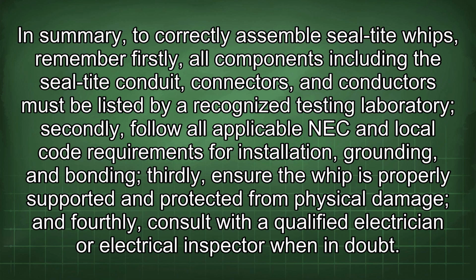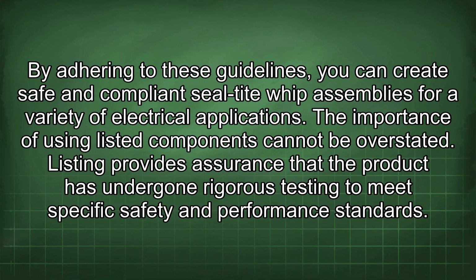In summary, to correctly assemble Seal-Tite whips, remember firstly, all components including the Seal-Tite conduit, connectors, and conductors must be listed by a recognized testing laboratory. Secondly, follow all applicable NEC and local code requirements for installation, grounding, and bonding. Thirdly, ensure the whip is properly supported and protected from physical damage. And fourthly, consult with a qualified electrician or electrical inspector when in doubt. By adhering to these guidelines, you can create safe and compliant Seal-Tite whip assemblies for a variety of electrical applications.